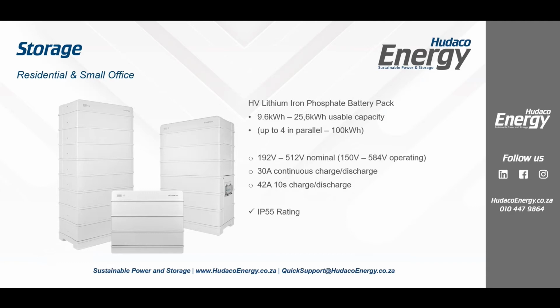deal with startup currents. So we can deal with startup currents on equipment, but of course, as you'll be aware, you can't maintain that for a long time. It's actually a curve that it follows, and the longer it is, or the higher it is, the shorter that time is. So you could maybe run 32 amps for a minute or 2 minutes or 3 minutes. Okay.